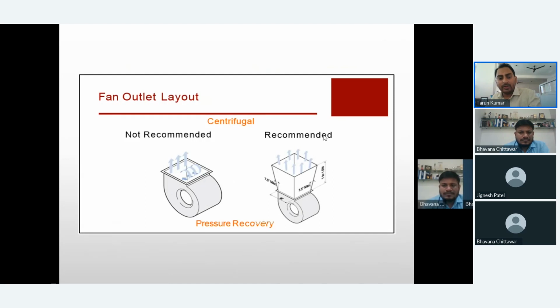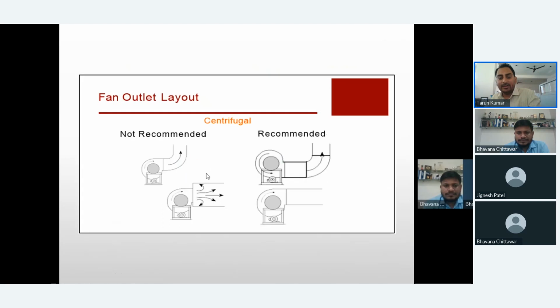At the same time, if you have a top discharge, you should not keep the space open, because back pressure will be generated and your power loss will be more. So we have to give some kind of duct arrangement at the top so that the flow goes in the right direction and no back pressure is generated from the same air. In the first not recommended photograph, they took a bend immediately upward. Rather than that, you could have used a 270-degree orientation of the fan, and your flow will be straight and you can get better performance from the fan.